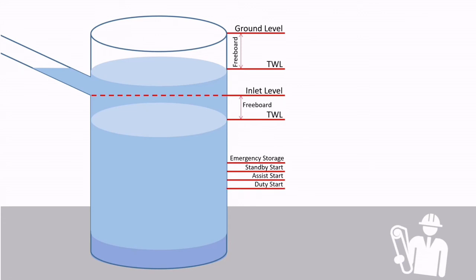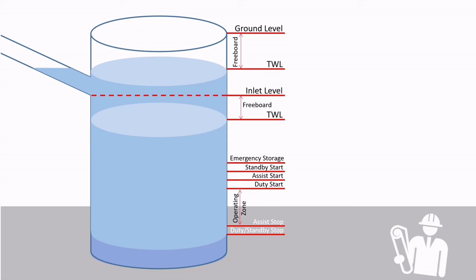Now using the formula, operating volume allows you to work out the stop level. If this is an assisted pump, then this will be the level for the assisted stop. If there is no assist stop, then this would be duty stop. However, in a situation where there is an assisted pump, then it is very important not to have all pumps stopped together, and the duty pump stop level is below the assisted stop level.